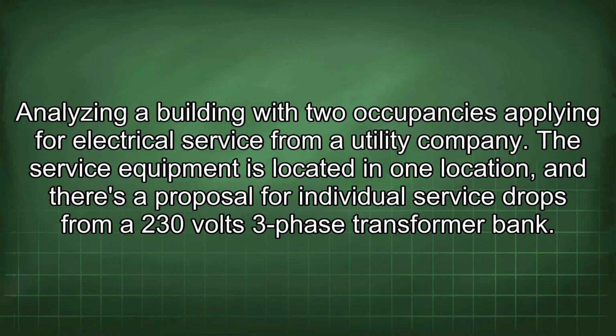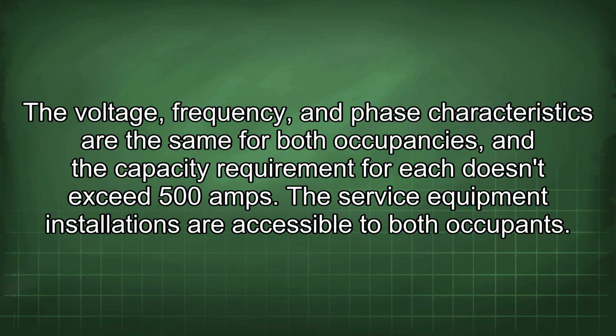Analyzing a building with 2 occupancies applying for electrical service from a utility company. The service equipment is located in one location, and there's a proposal for individual service drops from a 230 volts 3-phase transformer bank. The voltage, frequency, and phase characteristics are the same for both occupancies, and the capacity requirement for each doesn't exceed 500 amps. The service equipment installations are accessible to both occupants.